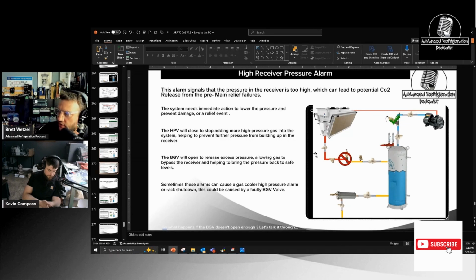If we have a high receiver alarm, which is usually the cause of a lot of high pressure issues, essentially your receiver pressure is higher than it needs to be. I've typically seen these about 50 pounds off of whatever the relief is. The BGV will try to open up to relieve that pressure into the medium temp suction, and then the HPV will try to close down. I've seen cases where the BGV itself is broken and stuck at a certain percentage, and I've seen guys replace the high pressure valve and the controller thinking that's the issue, and it all leads back to a broken driver or a broken BGV.